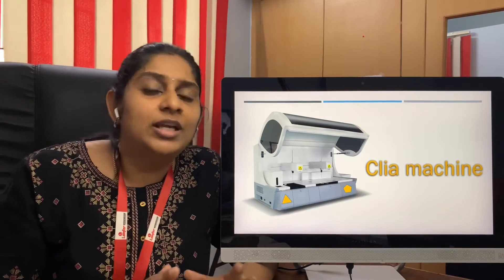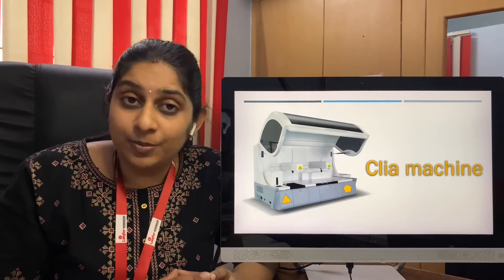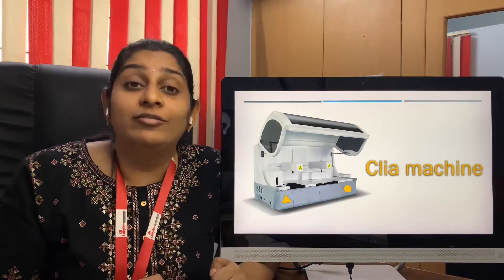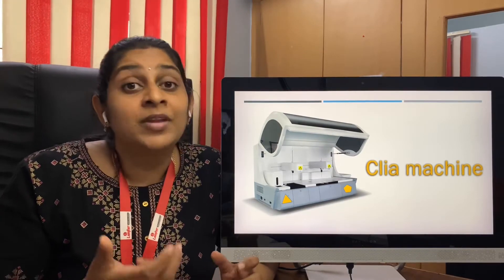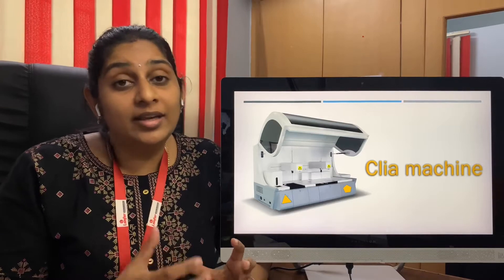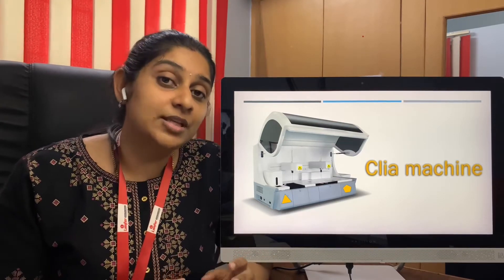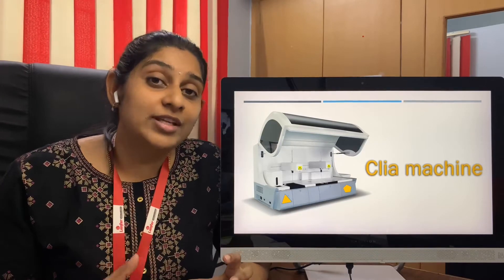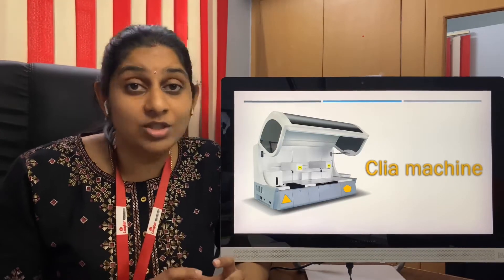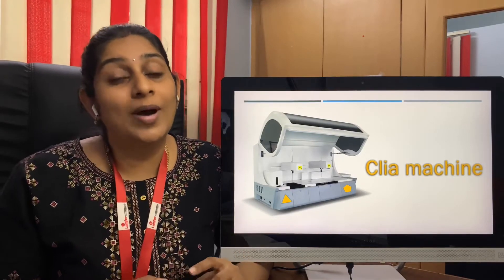So while choosing the machine, you can select what type of cuvettes your machine provider offers, which will very well reduce the cost in a newly starting laboratory. The next important thing to see in a CLIA machine is the starter solution. When you run samples in batches rather than one by one, the amount of starter solution used is going to be less compared to running samples individually.